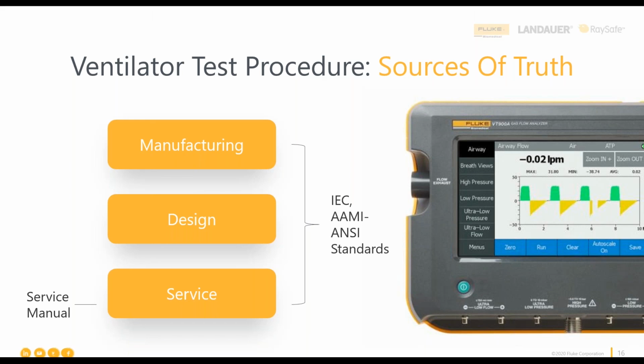The manufacturing engineer, they're trying to ensure that the product meets their design intent and performance before they ship it off to a customer. And then the biomed at the hospital is trying to ensure that the product still meets all of those requirements that are listed in the service manual. One thing to note here is that the service manual is really just a subset of the requirements in the larger regulation. So essentially, each one of these personas is testing to the regulations, just at different points or for different, never for a different reason, right? Other than compliance. Right. It's all about are they safe and effective for clinical use, and do they stay that way? And the international standards are a really good place, which is why we always start there when we're talking about how you use our test instruments, because it's critical in each of these different areas.